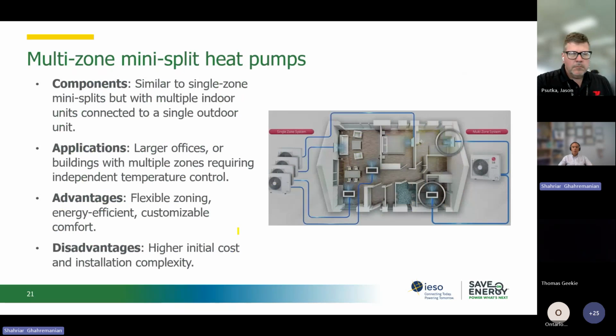Then we can have the same idea with one unit or two units, and then multi-zone mini split heat pumps. Again, it provides flexibility with the zoning. They are energy efficient, and they can customize the comfort, because maybe in one zone they want heating, and in another zone they want cooling at the same time. So we can have such a system. And then we can have multiple outdoor units, but again, the disadvantage is a higher initial cost, and the installation can become complex. So we need an expert to design such a system. But this is good for larger offices and buildings which require multiple zones with independent temperature controls.